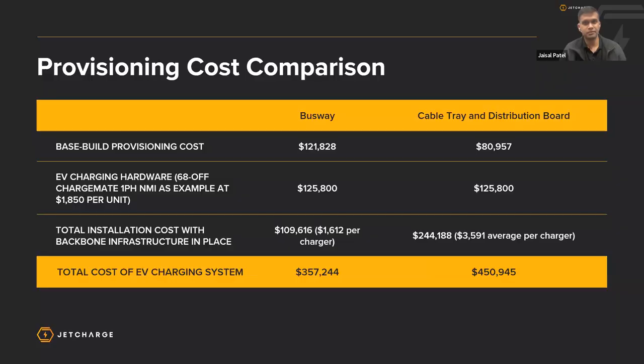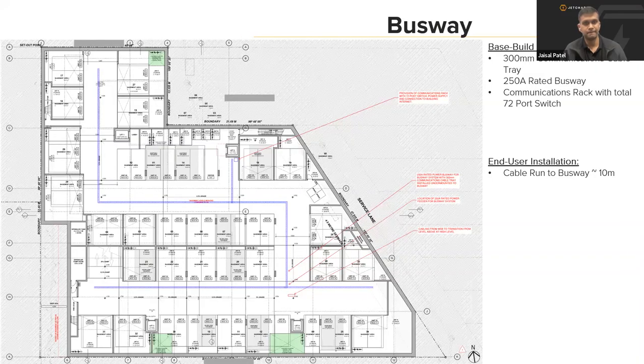With the busway method, we're essentially running the same reticulation throughout the car park with the communications cable tray being 300 mil as well, but we eliminate the distribution board as well as the power cable tray. The comms cable tray can either be mounted flush next to the busway or using a catenary arm mounted underneath the busway. With the shortest cable run and the longest cable run being exactly the same from the busway to the distribution board. Next slide.